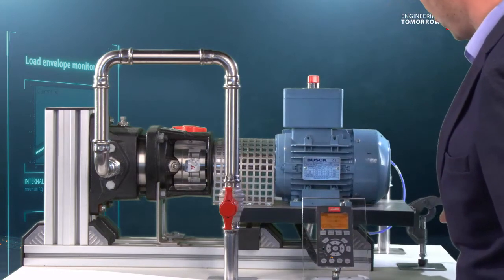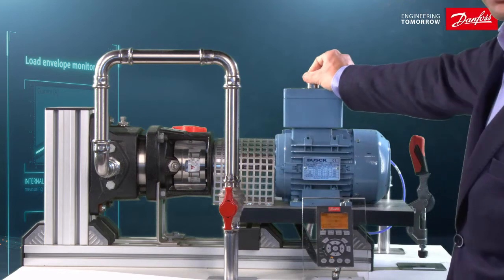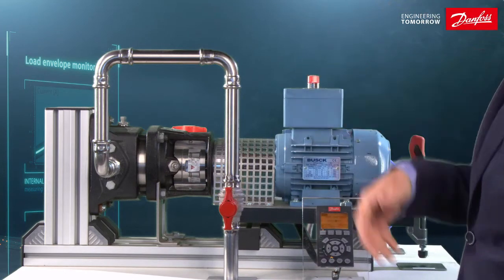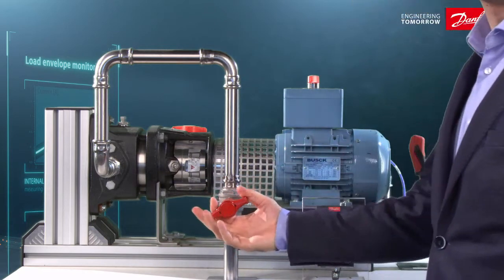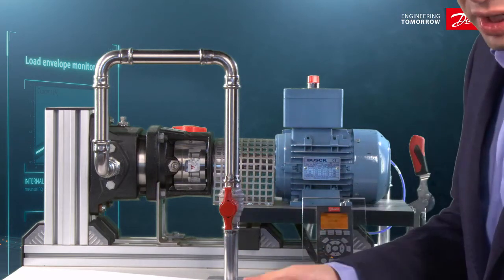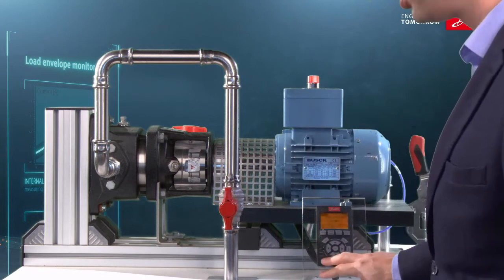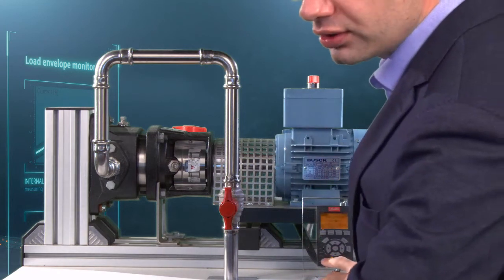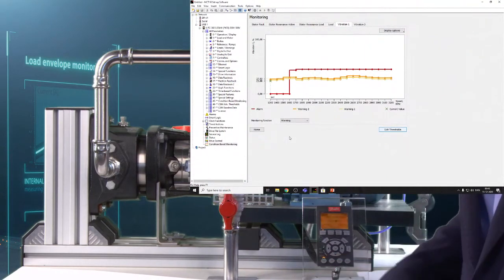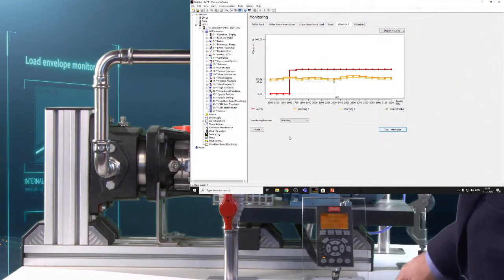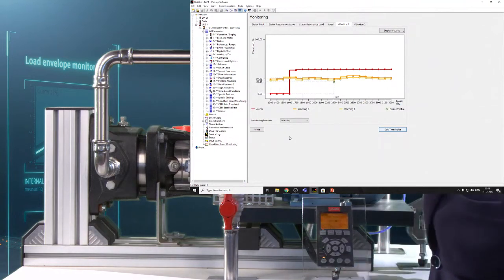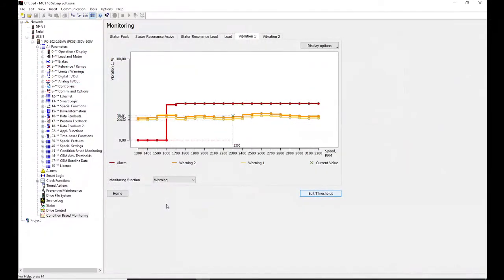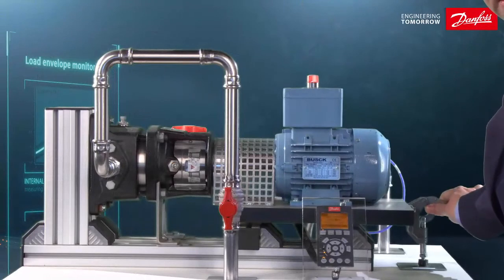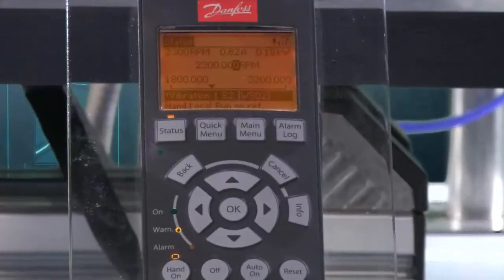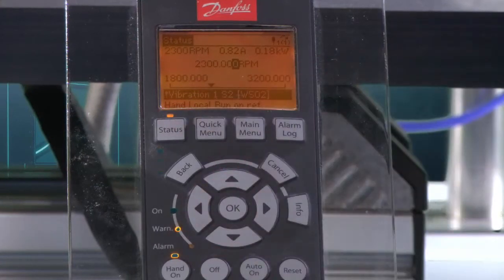We can generate a vibration fault by lifting the motor. We can make a single turn short circuit in the motor to generate an electrical fault, or we can change here the flow of water in the application. Now I will start the pump. You will get a bit of noise, more noise in the background. And meanwhile, while I'm doing this, I will also show you what happens with the vibration level, for example, if I activate this handle. So you see on the display the vibration level. Now I produce more vibration by inducing usually eccentricity by this handle. And then on the display of the drive, you see there's a warning here, vibration S2.